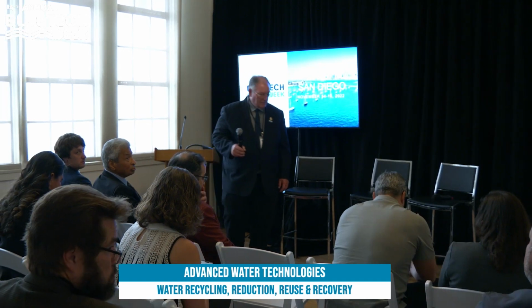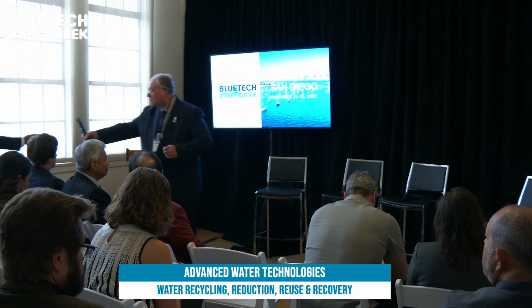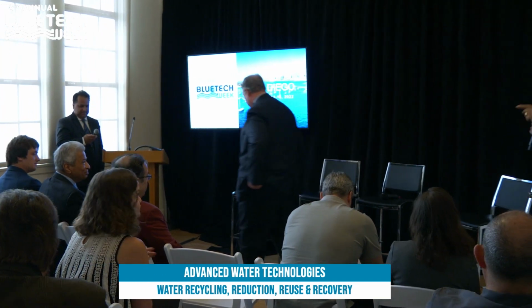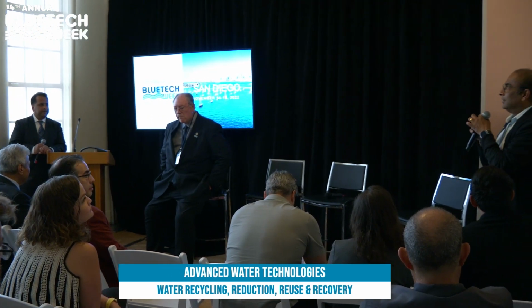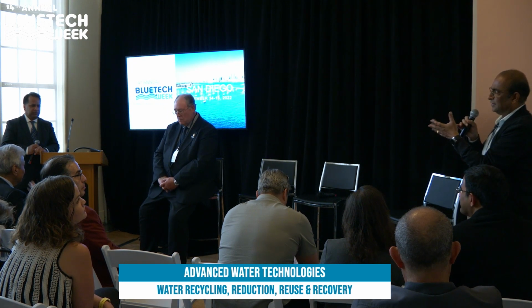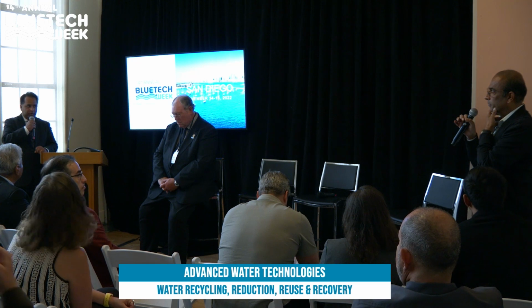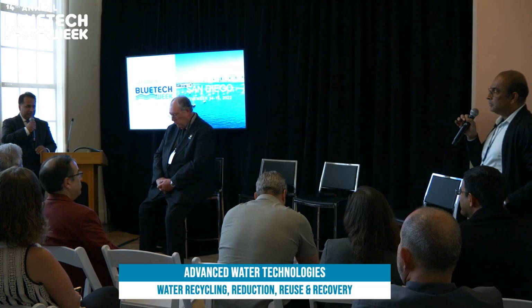Subir? I have a question for Jayesh. One thing you mentioned about very high concentration brine treatment with RO: when you mentioned that you will take it from 12% to 20% TDS, 22%, yeah, are you planning to do that in a cross-flow mode or dead-end mode? It has to be a cross-flow mode, because at that high TDS you don't want to be dealing with concentration polarization issues.